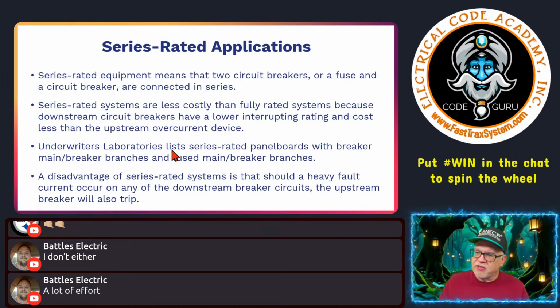Underwriters Laboratories lists series rated panel boards with breakers in the main breaker branches and fused main breaker. So this is very common. That's how they evaluate them. And that's probably what you're going to run into the vast majority of the time.